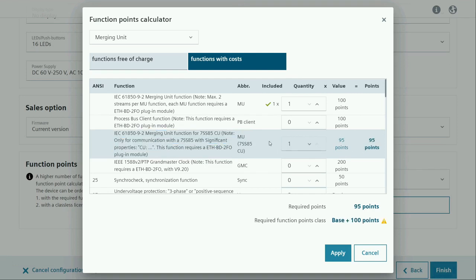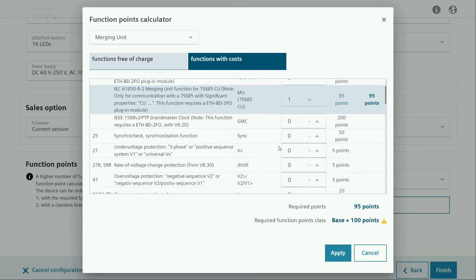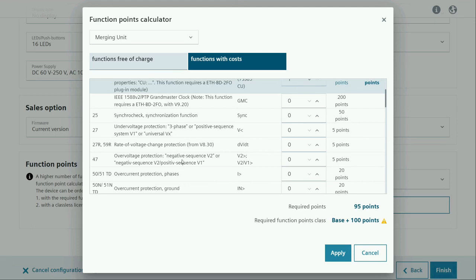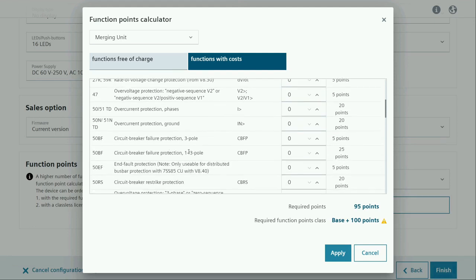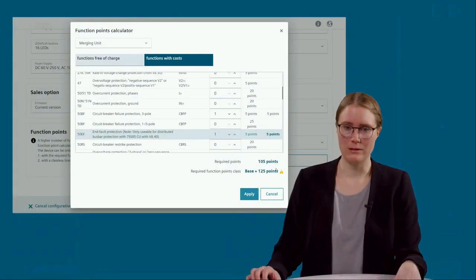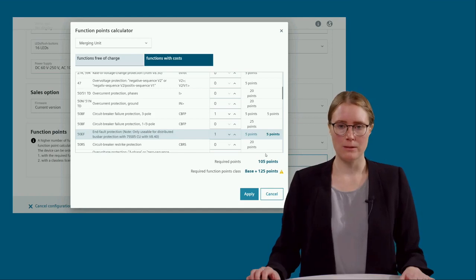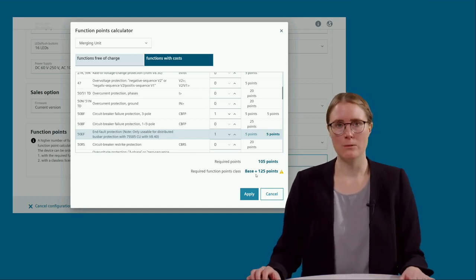So this number needs to be increased to 1. And once again, you can add additional protection functions. In my case, I only want to add the circuit breaker failure protection, 5 points. And I want to add the function points for the end fault protection. And here, maybe to note the difference from the solutions before, only for the 7SS85CU solution, the end fault protection is activated in the merging unit, and that's why I have to pay the function points here for the merging unit. Then I have overall required function points of 105, which means I need a device with function point class 125.